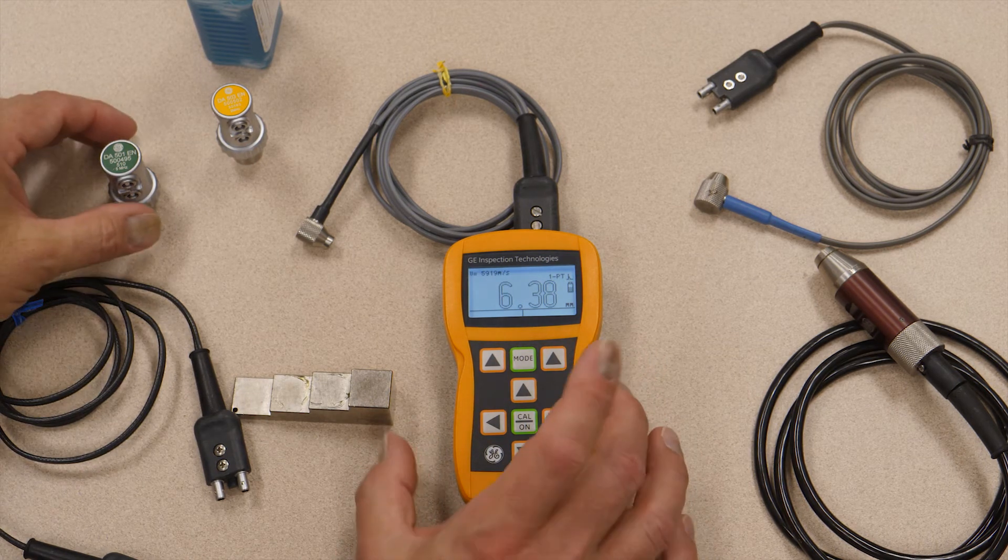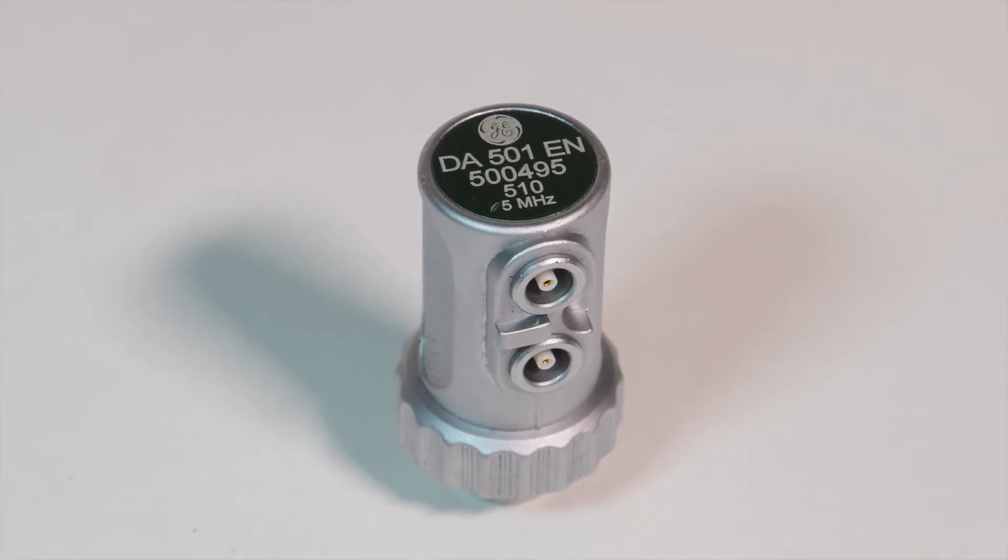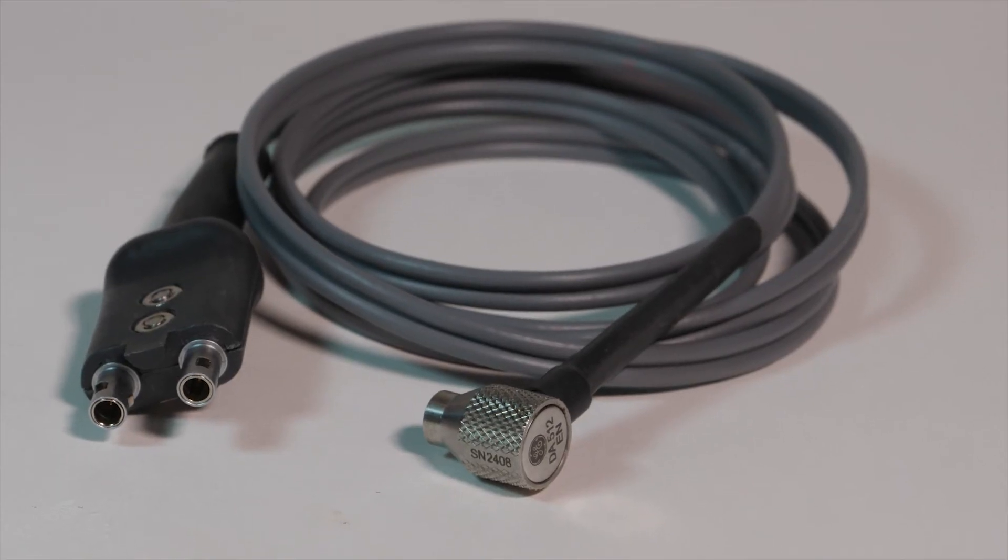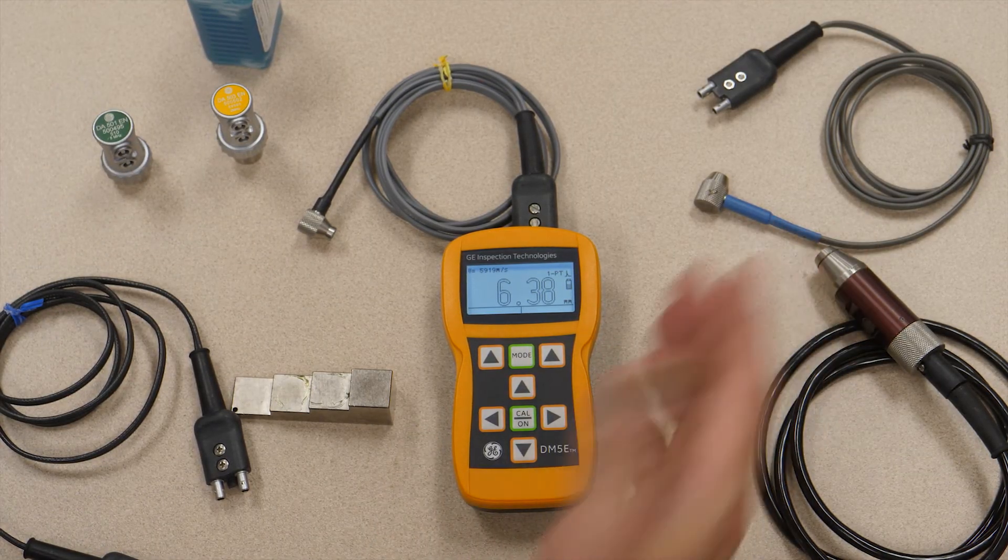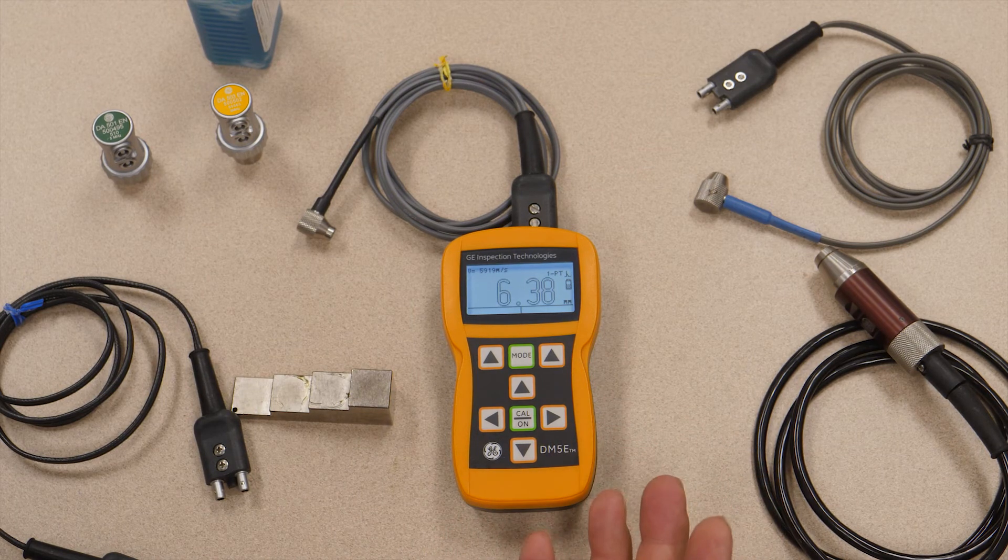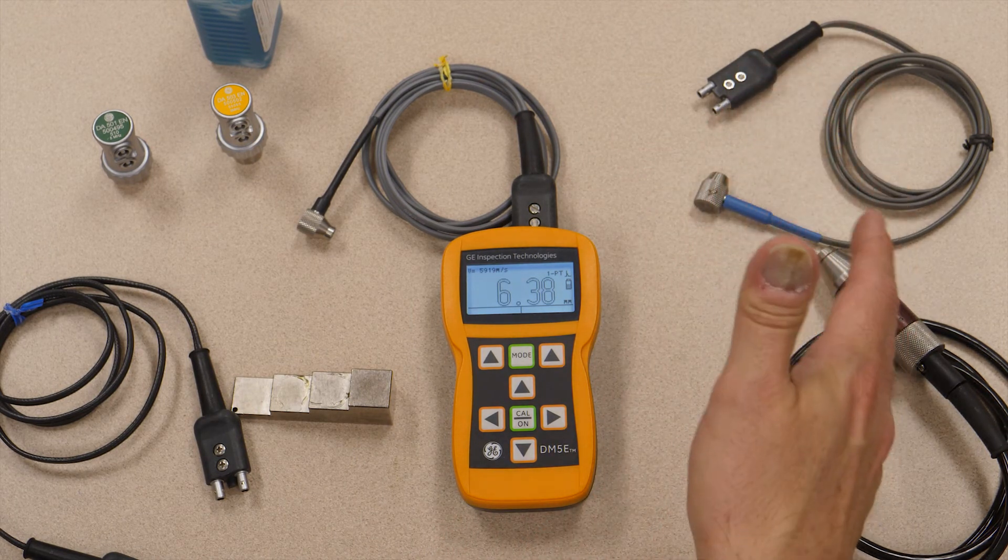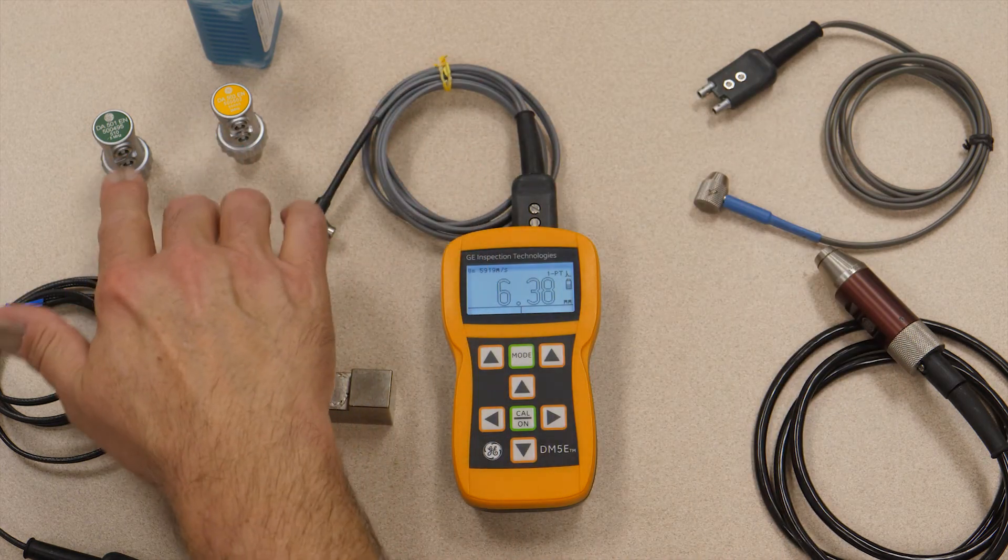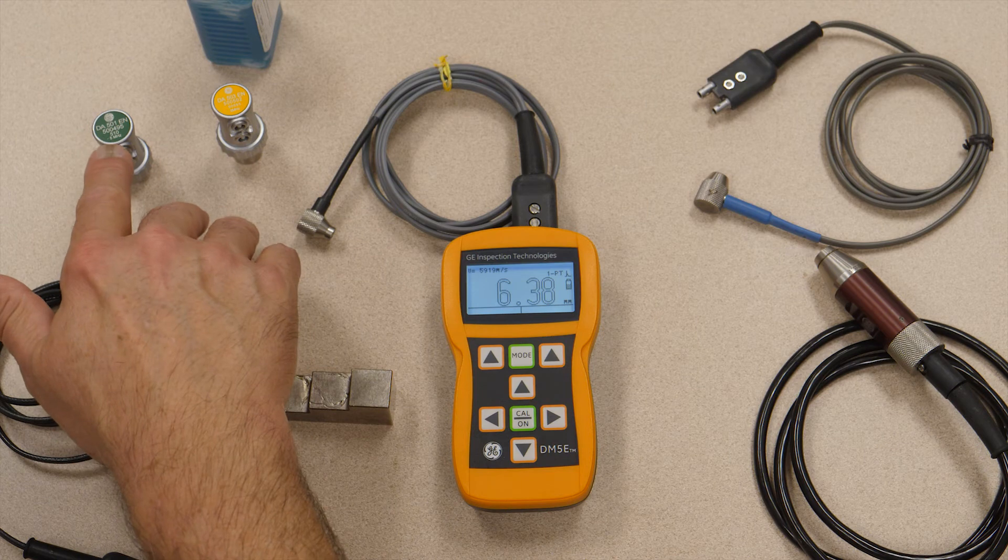Now, the dual multi-mode is only supported on this instrument with the DA501 probe and the DA512 probe. So a common question we have, folks will buy a DA503 or an FH2E, very commonly used probes, but only the regular dual mode is supported on these other probes. If you want dual multi to measure through thick coating, DA501 or DA512 takes care of your dual multi needs.